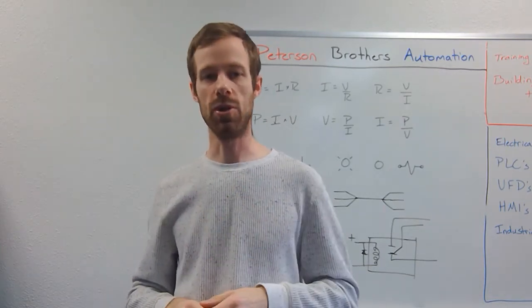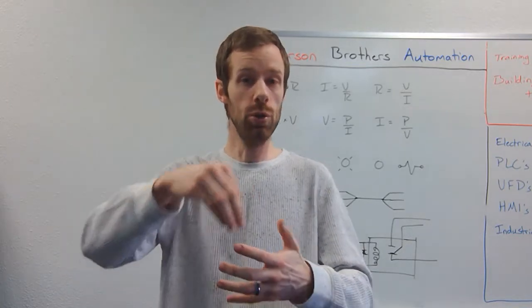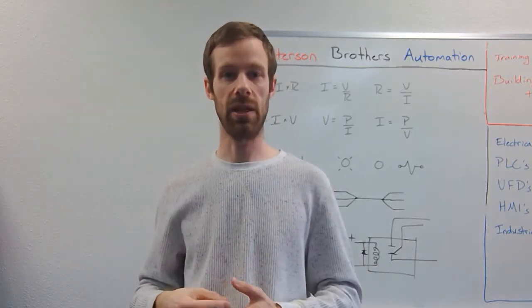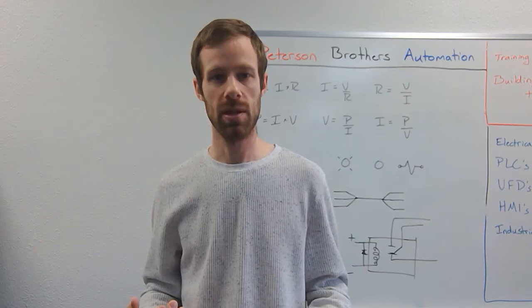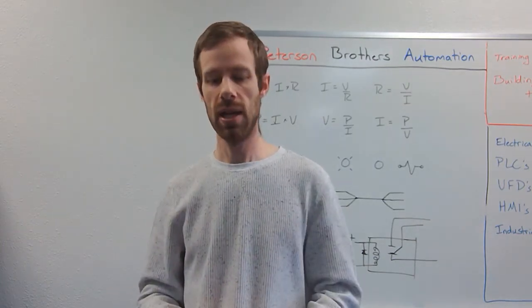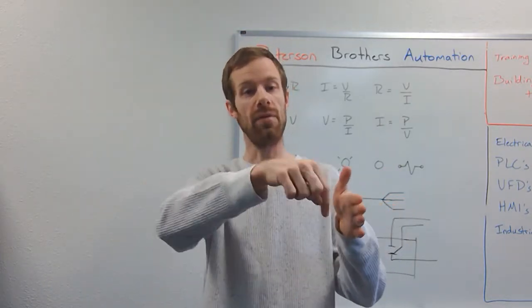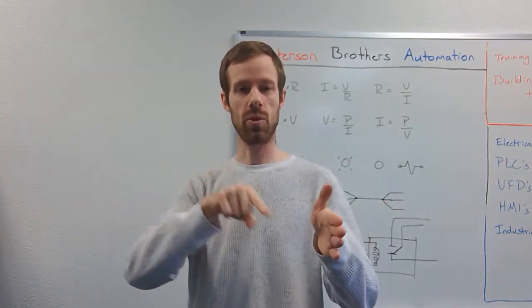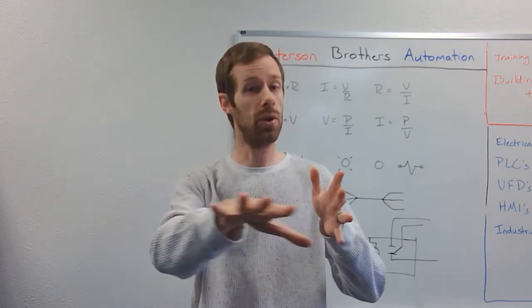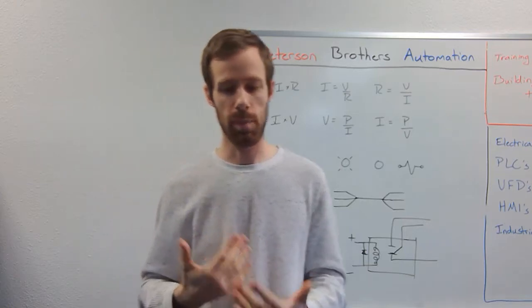However, power distribution for control systems, lower voltage, usually doesn't need to be huge screw down terminal lugs for carrying 50 to 100 amps. They're meant for carrying a few milliamps, small circuits. So we can get away with these small terminal strips that have a bunch of jumpers placed inside of them, and now 24 volts gets sent into it, and 24 volts can get sent off to hundreds of different devices if we need it to. So that's the parallel device.